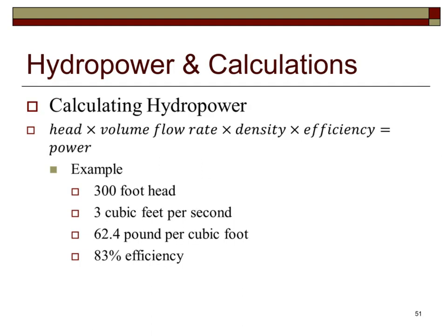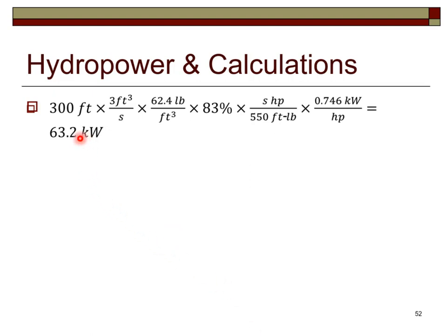In this example, we calculate the power from a 300-foot head. Water weighs 62.4 pounds per cubic foot, efficiency is 83%, and flow is 3 cubic feet per second. We multiply 300 ft × 3 ft³/s × 62.4 lb/ft³ × 0.83, then divide by 550 ft·lb/s per horsepower, and multiply by 0.746 kW per horsepower, arriving at 63.2 kilowatts.